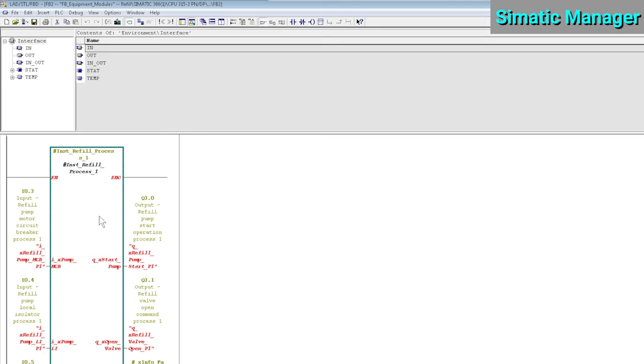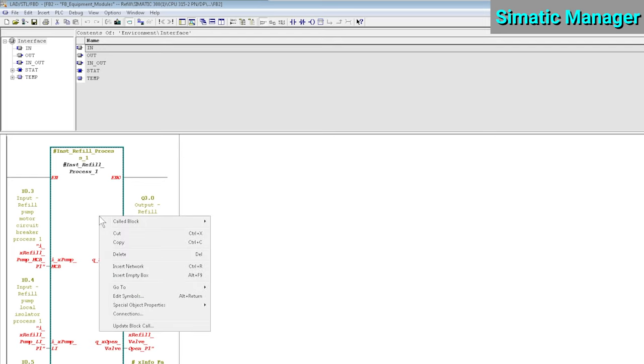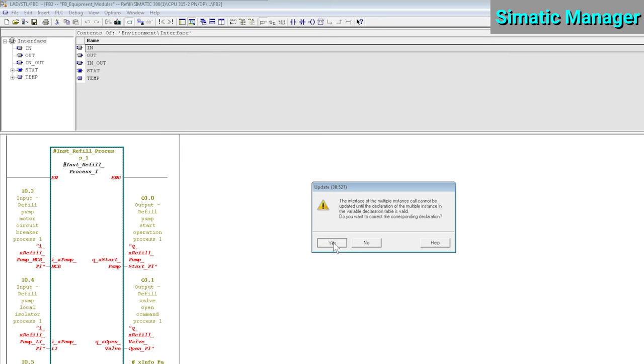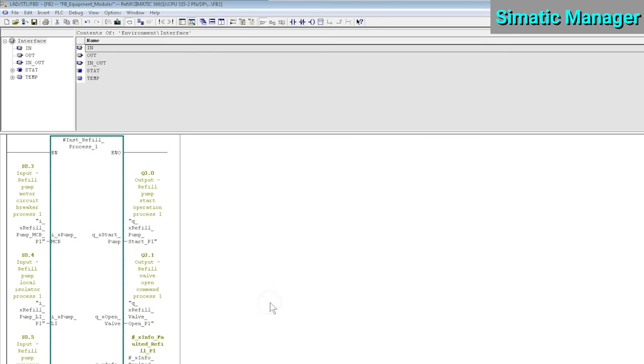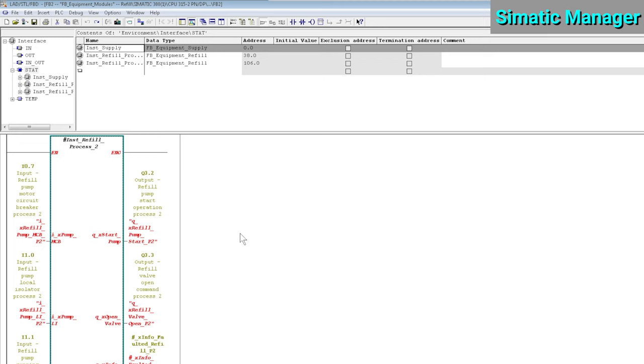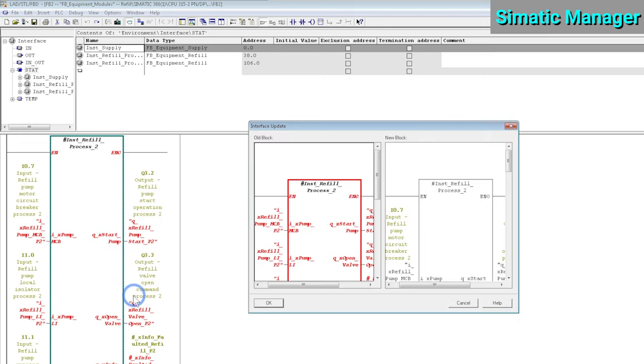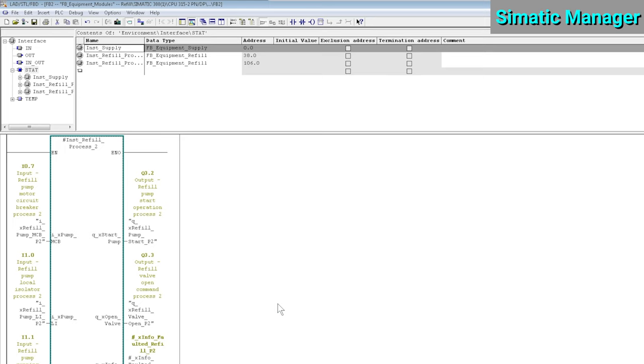We do that by right-clicking on the block itself and selecting Update Block Call. This function block is called two times here, once for Refill Process 1 and a second time for Refill Process 2. So we need to update the block call from Refill Process 2 as well. Now that we've updated all block calls, we can download the function block itself and both instance DBs. If you only downloaded your function block and forgot to update your block calls and download your instances, then there's a very real probability that your function block logic will not work anymore after your download.